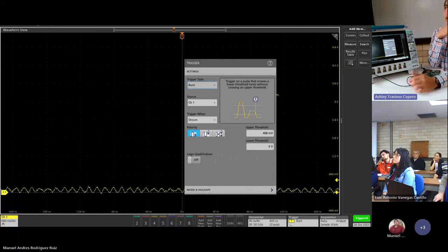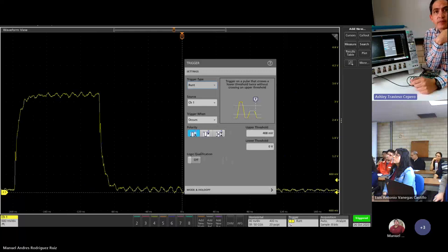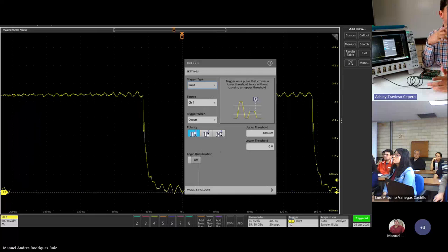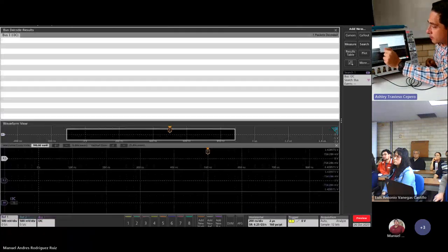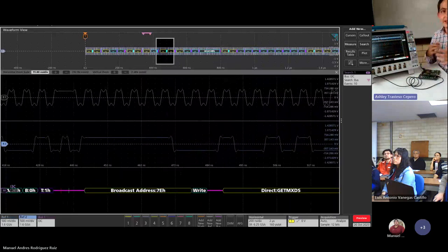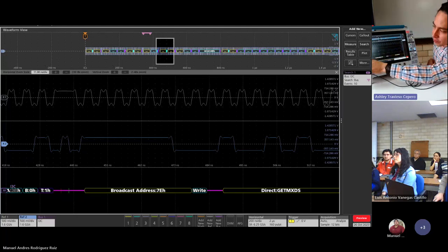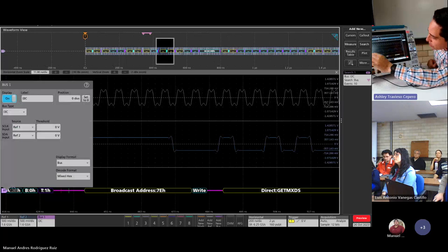But what's the idea? The difference between the analog channels and digital channels: the analog one is going to show all the noise on your signal. As an example, if I try to capture a digital signal, I'm going to move back in a moment, but just to show this. Right at the top, it's the digital signal, because it is a pattern of data, okay? And if you want to show the analog visualization, you will be presenting all the noise there on the signal, okay? But if you ask the same of a digital channel signal, let me try to show that.